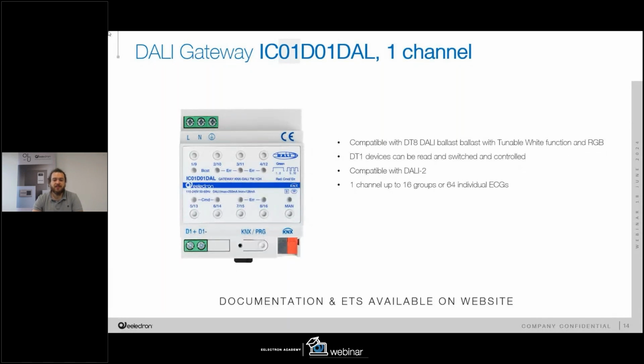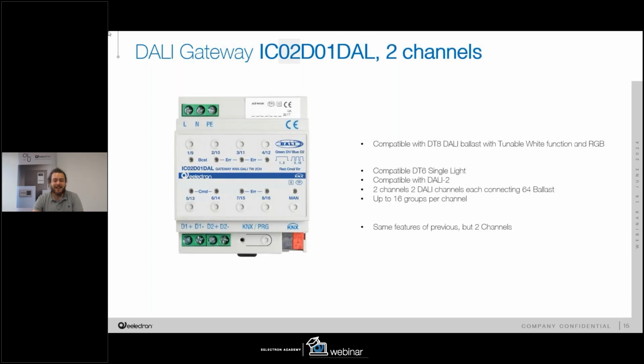Going ahead, we have the IC02D01DAL, that in this case is the same gateway, but as we can see also from the picture in the lower left corner, we will have two different DALI buses inside the device. This means that we can wire up to 128 DALI ballasts. This is because we have two different DALI buses, and this means that we can group them up to 16 groups for each DALI bus. Again, as I said before, with this gateway you can control any kind of ballast without any issue regarding the classic DT0, 1, 6 and 8. And again, you can control DT0 and DT1 ballasts, but without any analysis regarding the emergency lighting system.